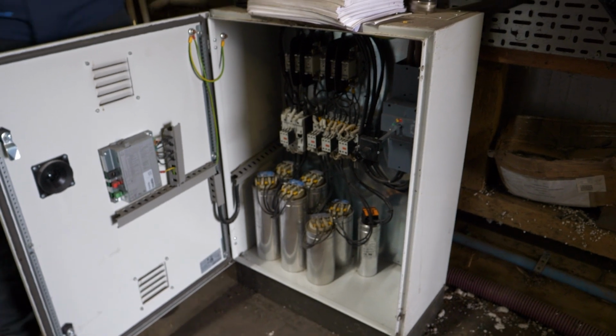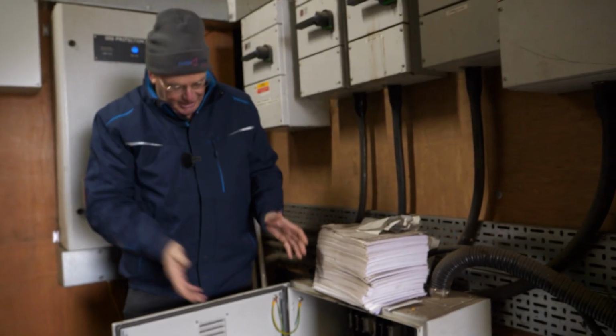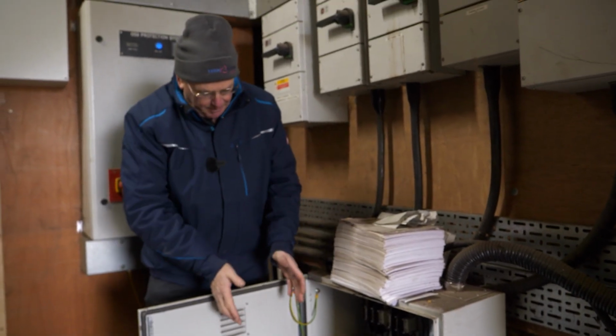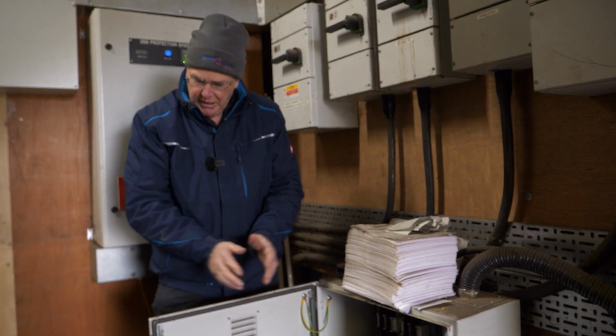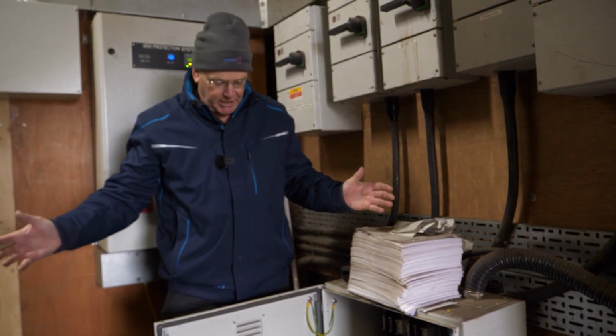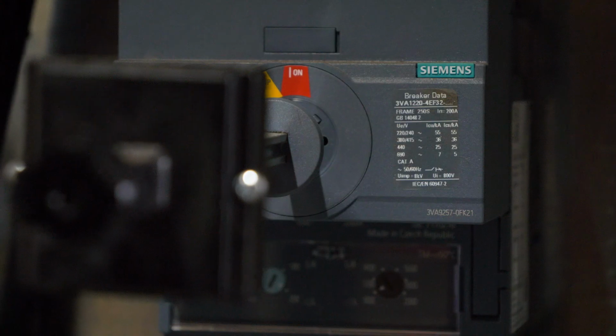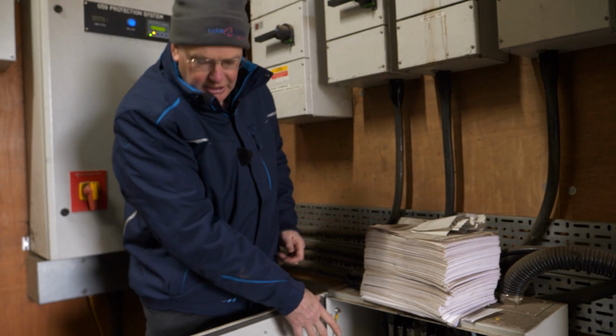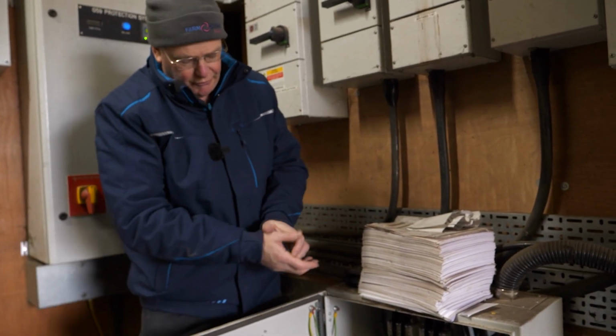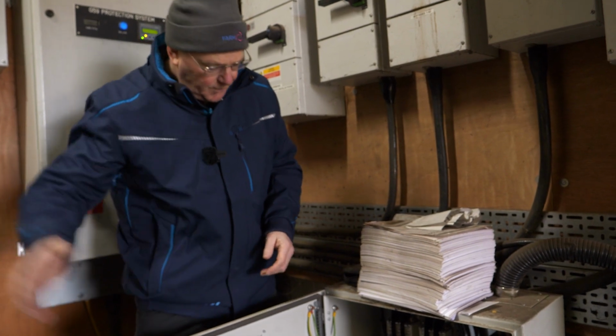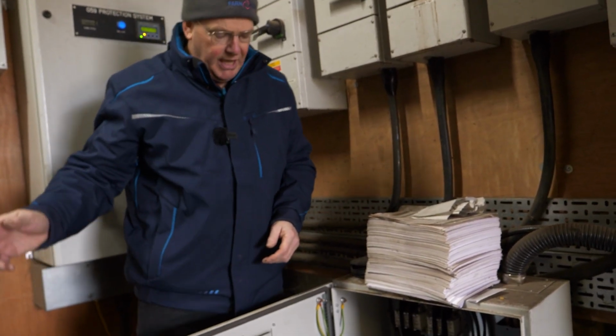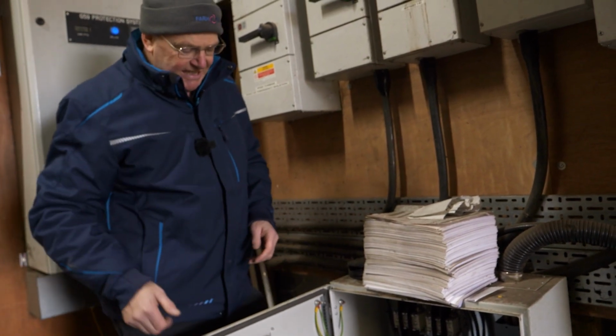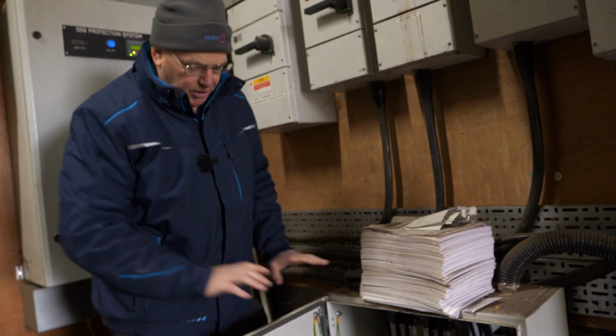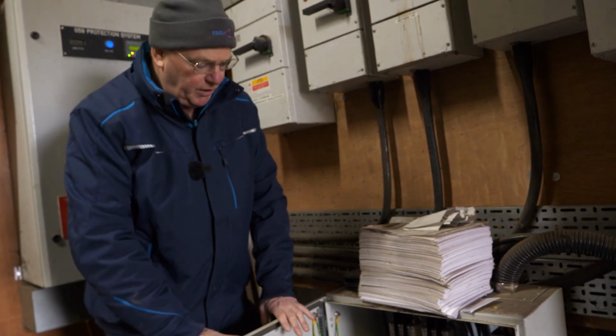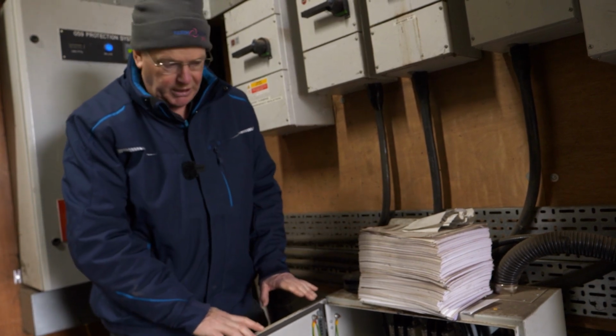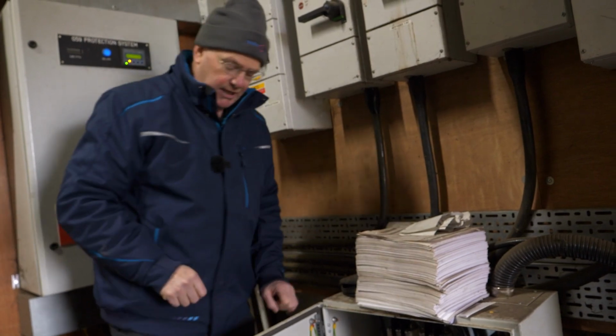Power factor correction is a series of capacitors. What happens is that when the electric motor creates a magnetic field 50 times a second, when it collapses, the reactive power that's created comes into here. This is like a header tank for a water system, filling and emptying 50 times a second when running, taking all that reactive power out of the system. When I turn it back on, before it starts working, you'll see the actual power factor without this, and then once it starts, you'll see what it is when it's 1. But in the meantime, we'll have a look at that unit here.